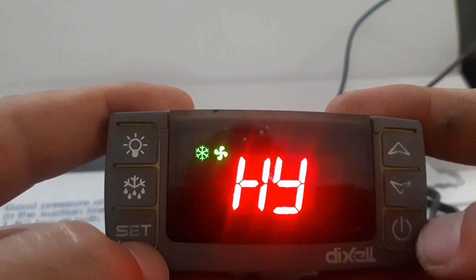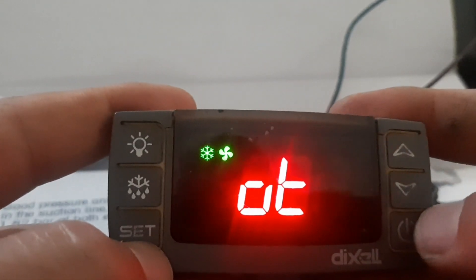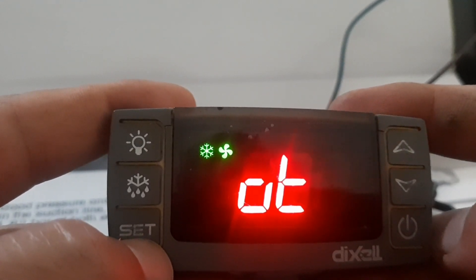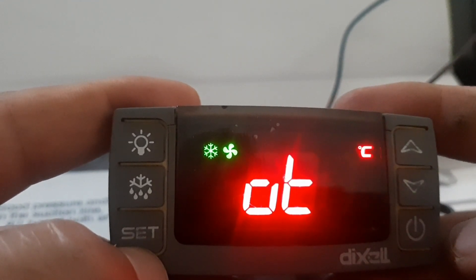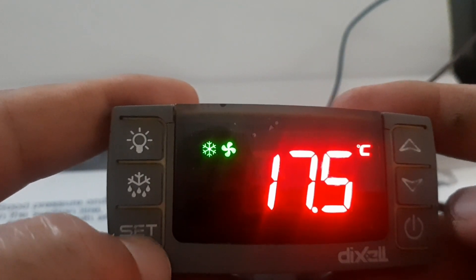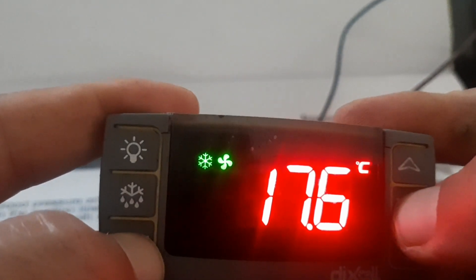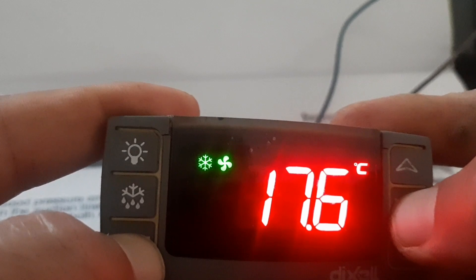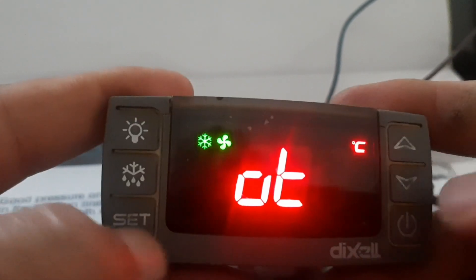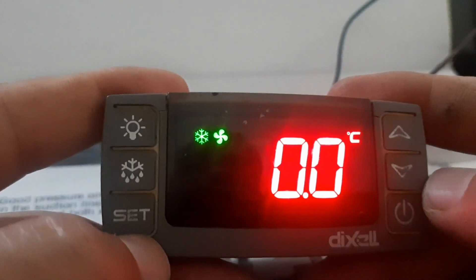You will see HY, which is the differential — we'll talk about that in the next video. In this video we discuss calibration. OT is the sensor calibration parameter. For example, if your cabinet temperature and the display temperature are different, you can add a value to the sensor. Navigate to OT and press Set to enter sensor calibration on the Dixell.